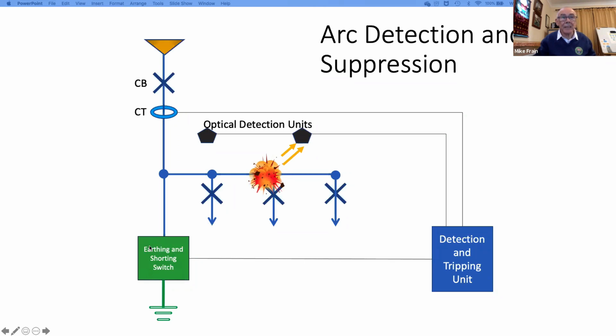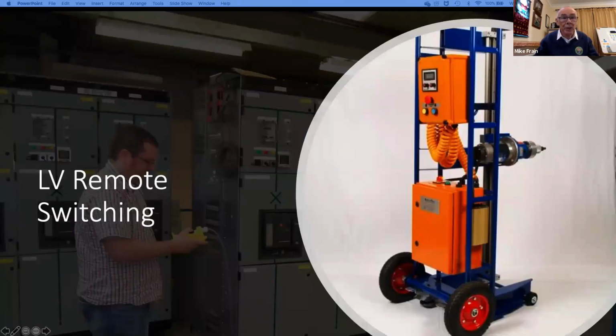Within 4 milliseconds, the earthing and shorting switch will apply an earth and make the equipment safe, and an upstream device will either trip of its own accord or be sent separate tripping signals to disconnect as well. LV remote switching is another thing that people are clearly asking for more and more. On the left-hand side, you can't quite see him, but he's holding a lanyard to remotely switch some equipment.